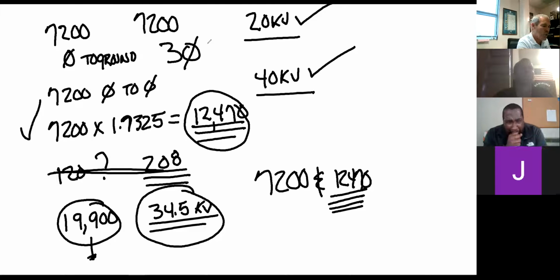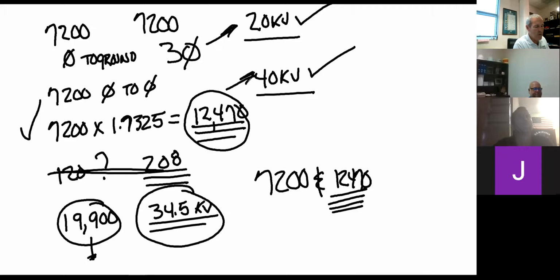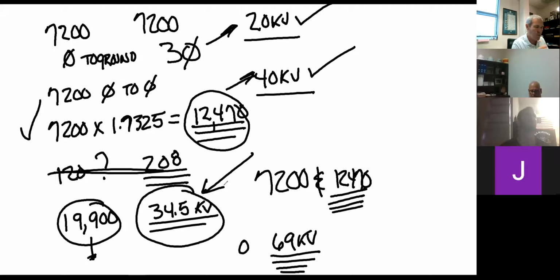Our organization, 20 kV gloves, 40 kV gloves. We travel up to, and I know we use this example a lot, we travel up to Sandy, and we meet with their safety specialist right there. And their intentions were, well, we're going to need you guys to work from 0 to 69 kV. What did I tell them? We don't have the safety gloves for that. Absolutely. You told them right off the bat, we are not insulated to 69 kV. We are insulated to 34.5 kV. That's as high as we can go. He said, no problem. Appreciate you letting me know. And we'll just give you assignments up to that voltage. You've got to know the system that you're working on and be prepared as far as the safety aspect of it.